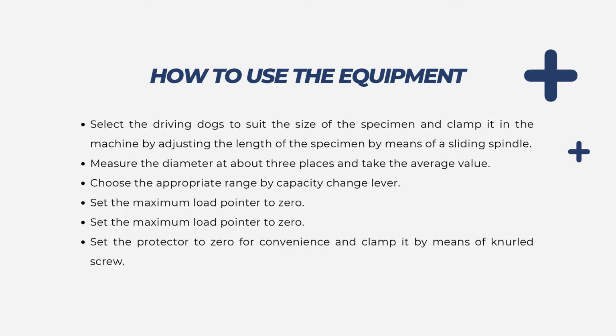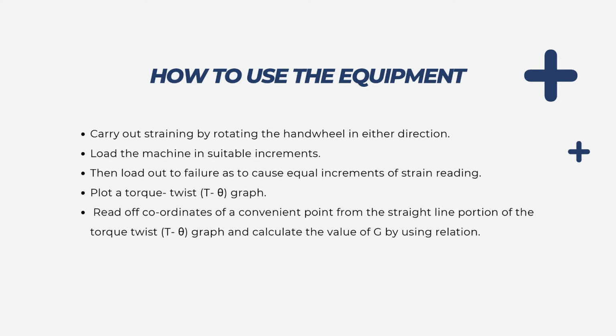How to use the equipment. Select the driving dogs to suit the size of the specimen and clamp it in the machine, adjusting the length of the specimen by means of a sliding spindle. Measure the diameter at about 3 places and take the average value. Choose the appropriate range by the capacity change lever. Set the maximum load pointer to 0. Set the protractor to 0 for convenience and clamp it by means of the knurled screw.